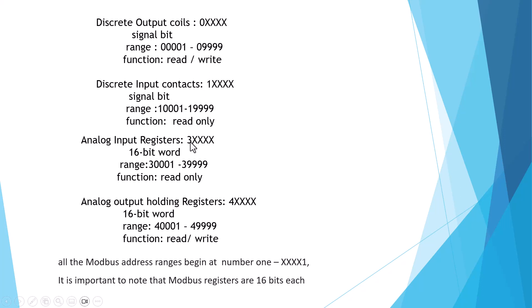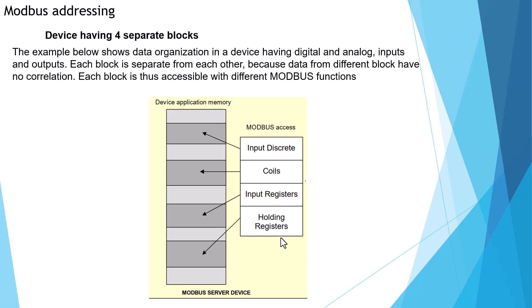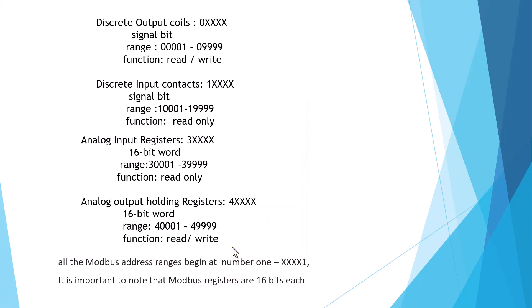The analog input register starts with three for the leading digit. It is a 16-bit word — analog input — ranging from 30001 to 39999. The function is read only. The analog output holding register starts with four as the leading digit. It is also a 16-bit word, ranging from 40001 to 49999. The function code is read and write.